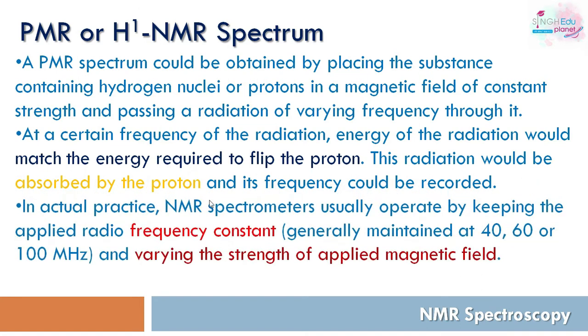In actual practice, the NMR spectrometer operates by keeping the radio frequency constant and changing the applied magnetic field strength. So we have two cases: the principle method uses varying frequency with constant magnetic field, while the actual instrument uses constant frequency with varying field. Both methods allow us to record the HNMR spectrum.